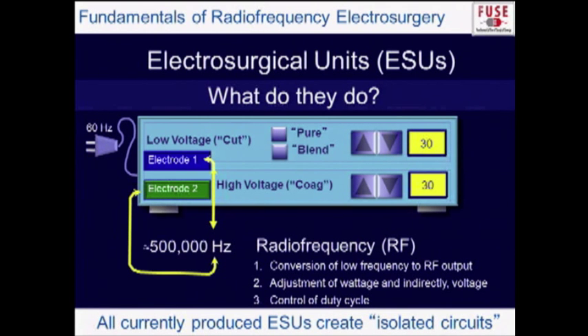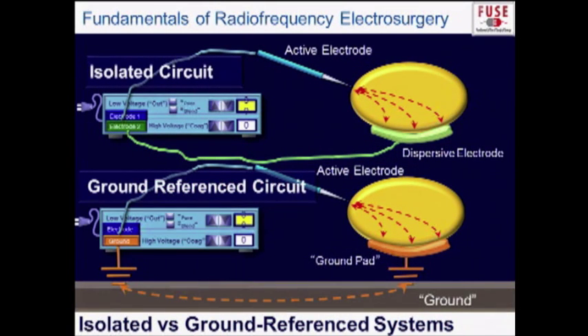All generators have an isolated circuit. There probably hasn't been a ground-referenced generator sold in this country for operating room use for 30 or 40 years. In a ground-referenced circuit, the pad is not connected to the generator — the circuit completes through the ground. But all generators you use today have a direct connection to the generator. These are isolated circuits, and these are not grounding pads — they are dispersive electrodes.